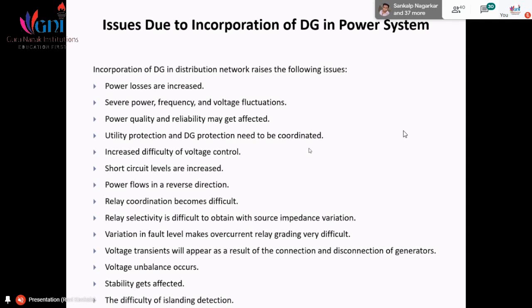Then next is the difficulty of islanding detection. This is a major problem when we have a grid-connected distributed generation. Islanding is the case where your distributed generation gets separated from the utility and feeds the load individually. The utility and the DG are connected, but that interconnection gets interrupted, and the DG individually feeds the load. So that operation is called islanding operation.